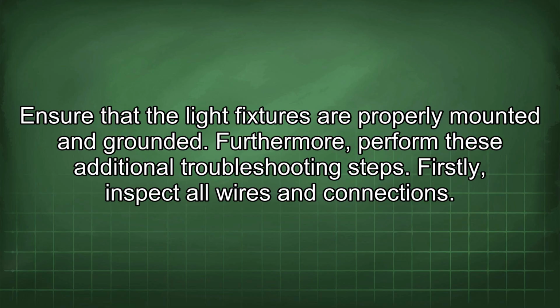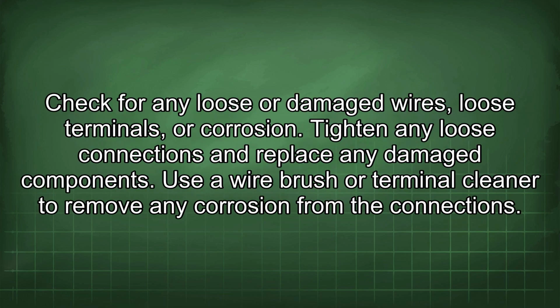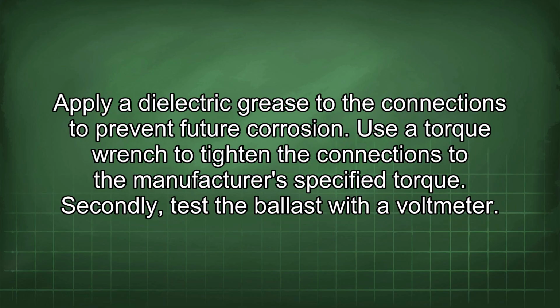Furthermore, perform these additional troubleshooting steps. Firstly, inspect all wires and connections. Check for any loose or damaged wires, loose terminals, or corrosion. Tighten any loose connections and replace any damaged components. Use a wire brush or terminal cleaner to remove any corrosion from the connections. Apply a dielectric grease to the connections to prevent future corrosion. Use a torque wrench to tighten the connections to the manufacturer's specified torque.